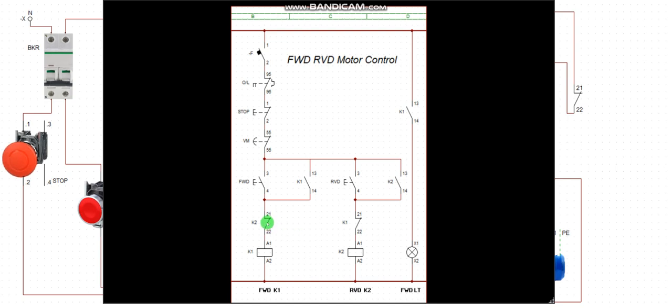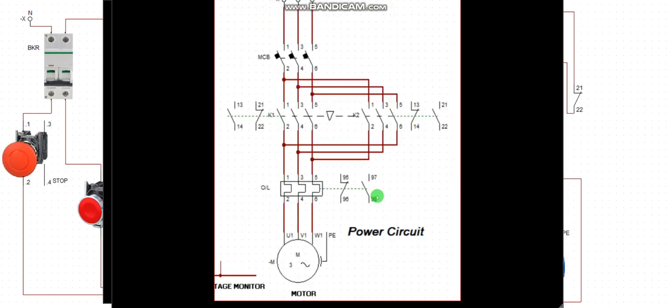Okay. So this one I use for interlocking. This one I use for interlocking. Let me see if I can show you. Take a look at this. When you buy this contactor, it's going to have these two auxiliary contacts embedded in them in some cases. Some of them come by default with normally open, this 13, 14. The number is 13, 14 globally. Some of them do not come with normally close, so you have to buy it and attach it to the body. But if you are opportune to get the one that has the two, better for you.